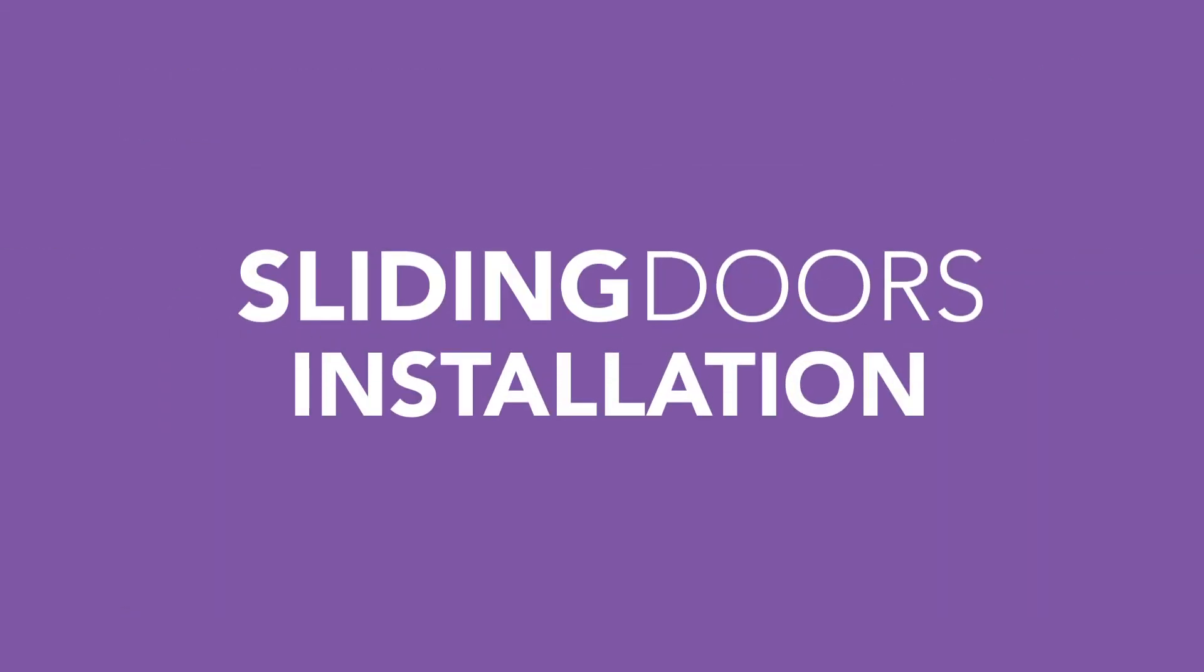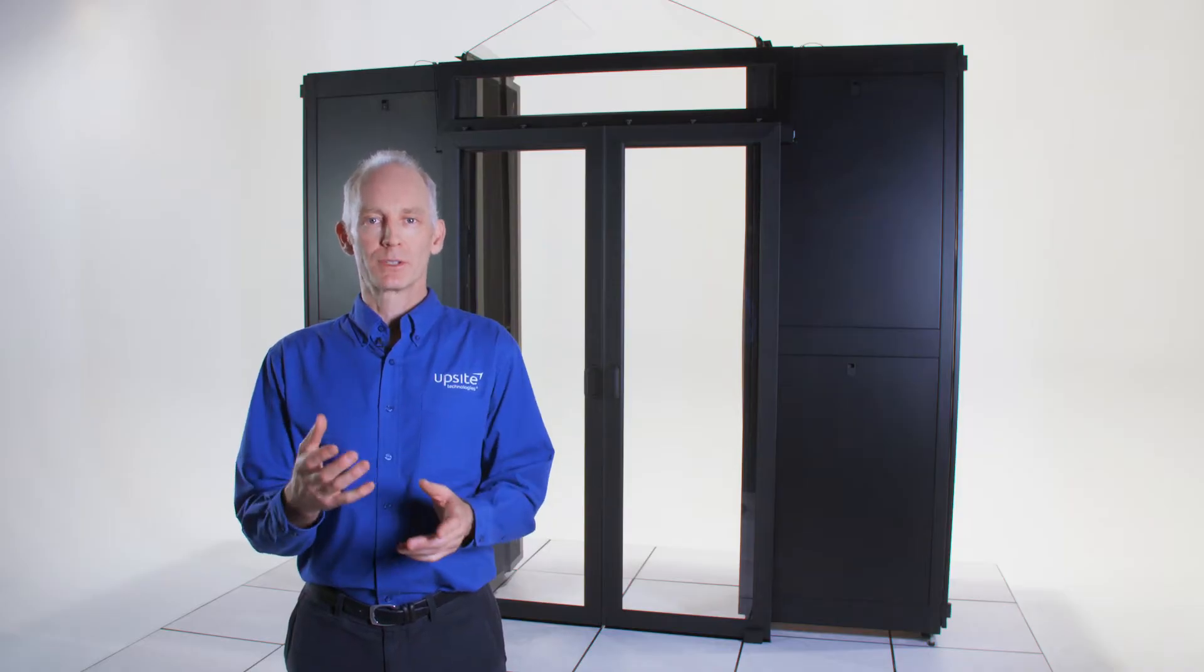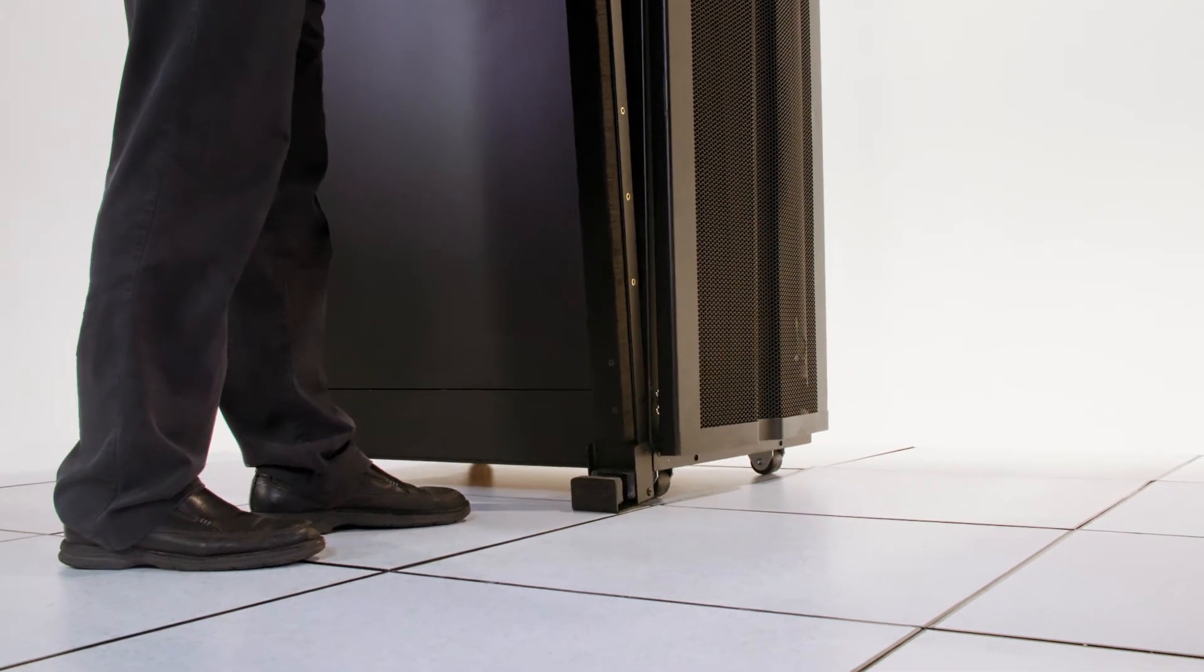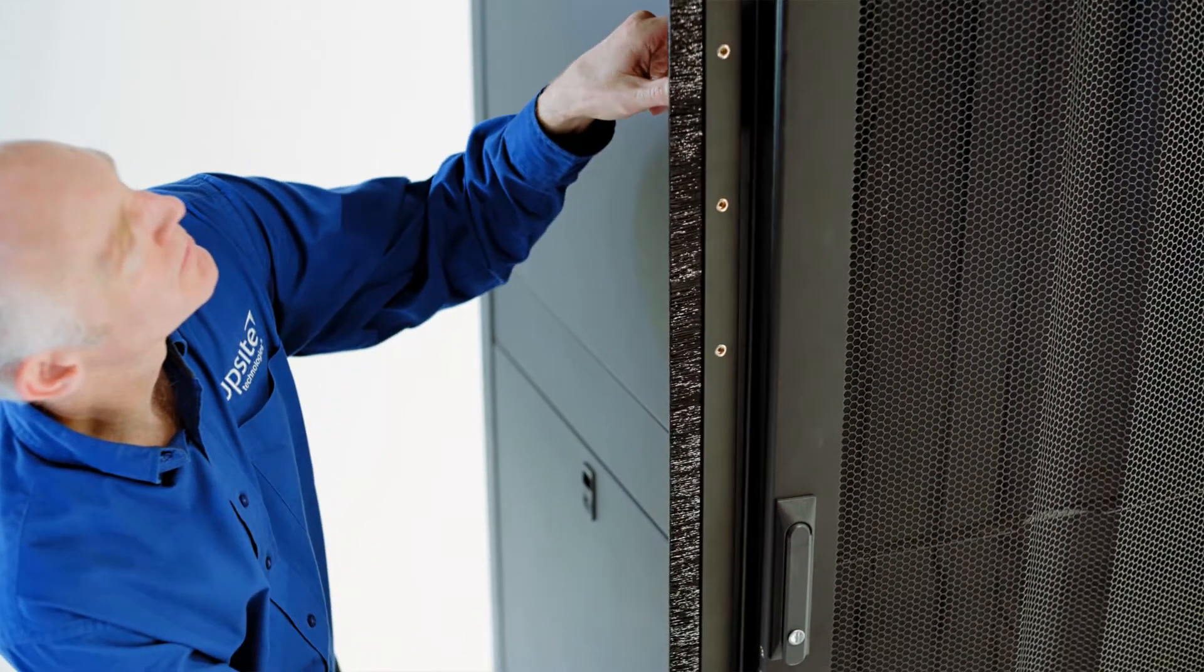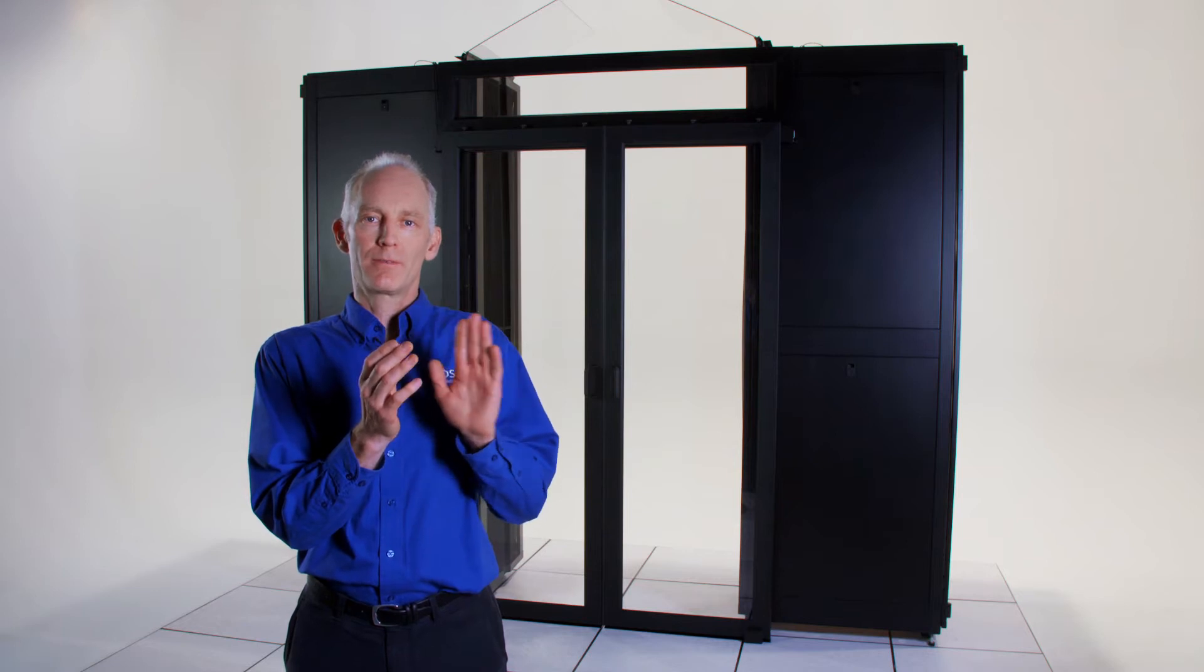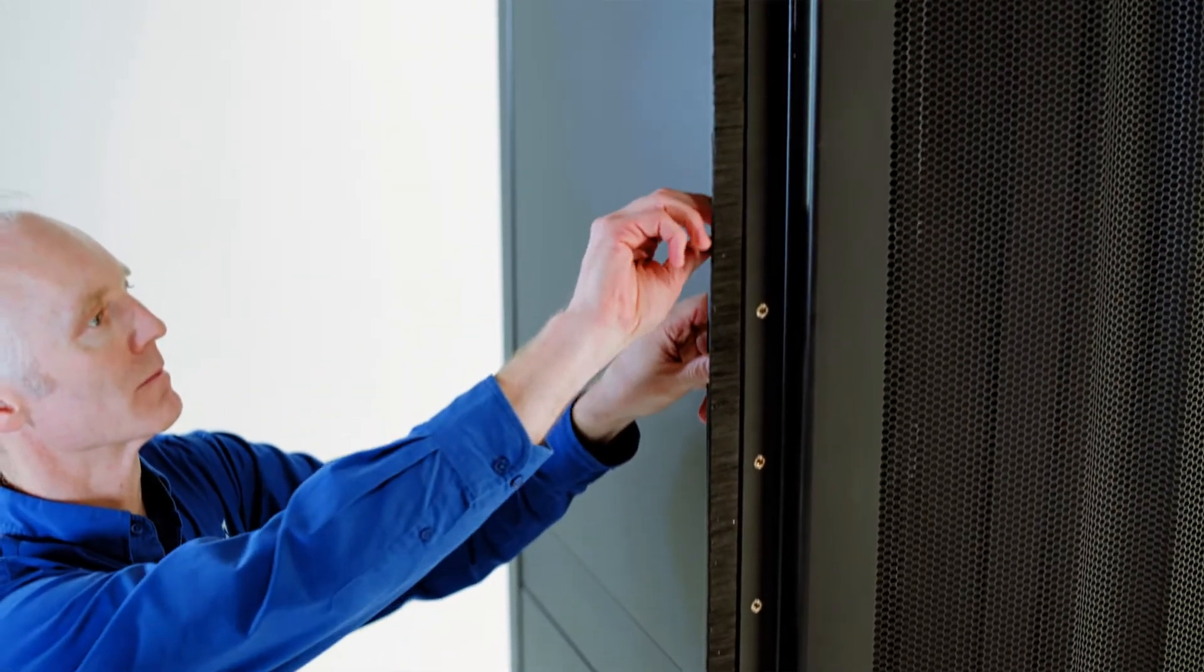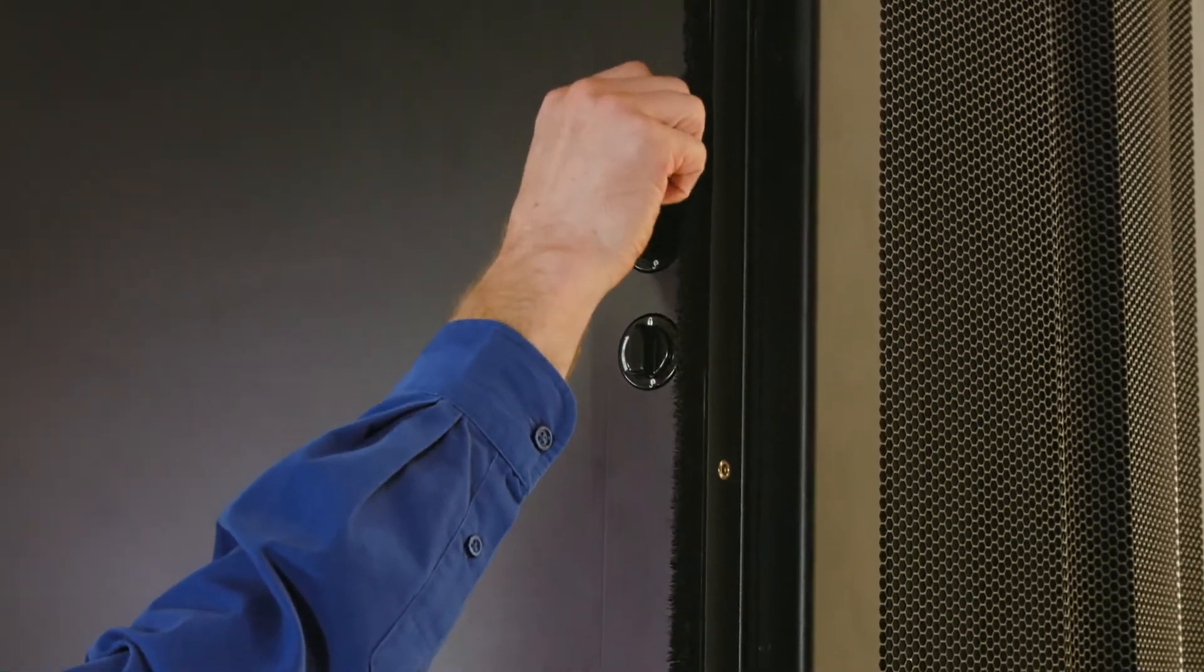Now I'd like to tell you about the installation process. The first step is to install the vertical posts. You set the base next to the cabinet and then tilt them up into position, aligning the front edge of the post with the frame of the cabinet. Then you can engage the mag switches to lock the post in place.